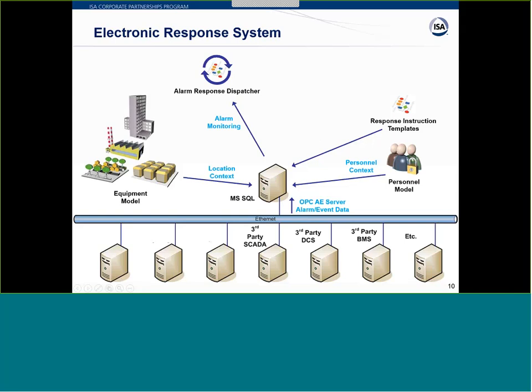And then the last thing, which is just as important as all of this, is the historical record of the execution of your alarm response. So who did what, when, where did they do it, how long did it take, you know, start time, end time, and so on, and any comments that were entered and messaging that was sent and things like that. So the historical record is very important, not only for regulatory compliance, but also for just improvement of the alarm response or the processes themselves.